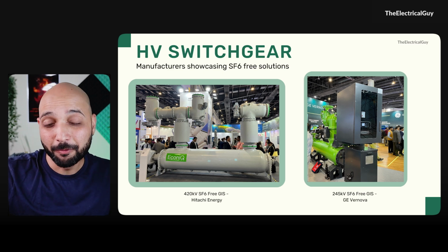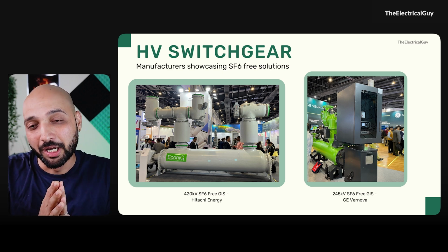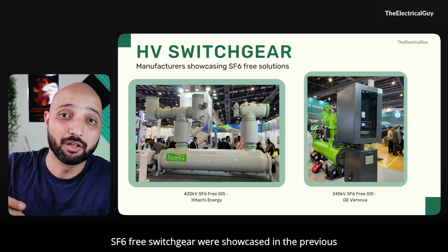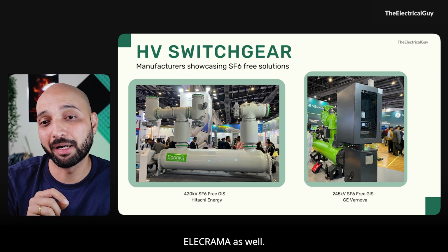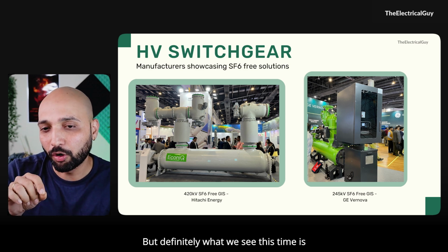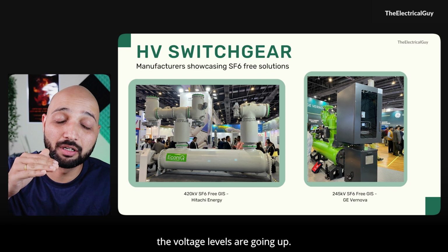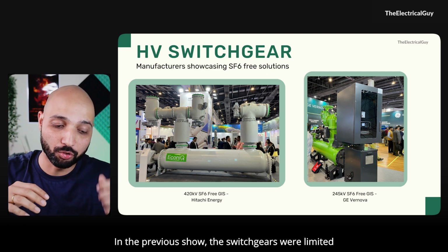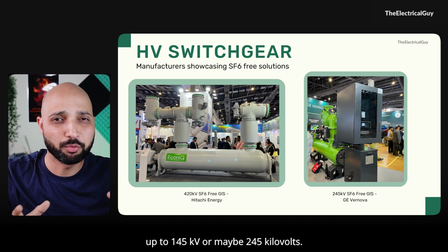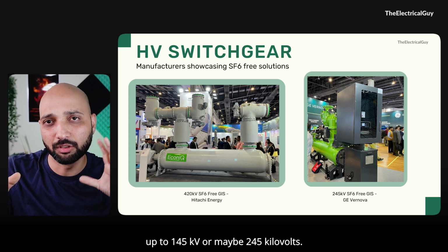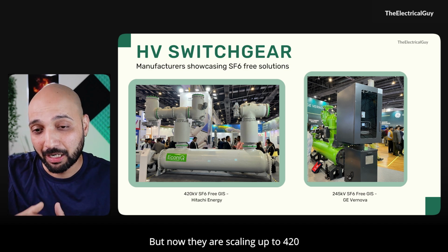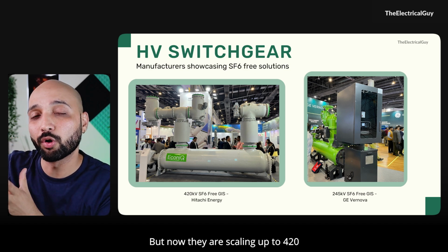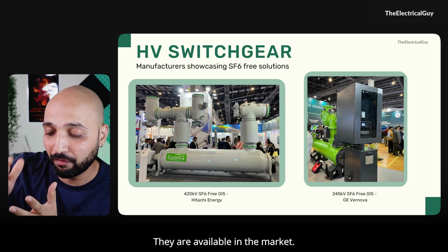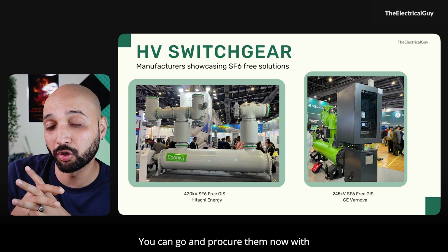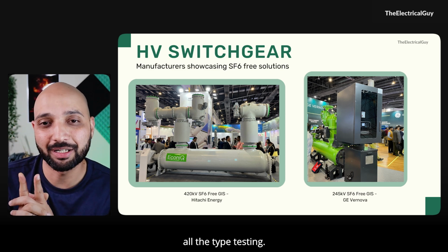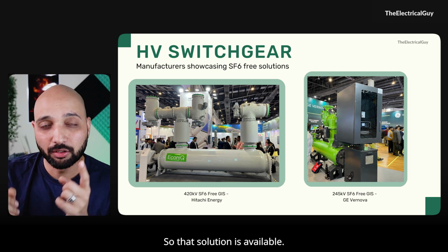Is it new? Well, no. SF6-free switchgear were showcased in the previous Elecrama as well. But what we see this time is the voltage levels going up. In the previous show, the switchgears were limited to 145 kV or maybe 245 kilovolts, but now they're scaling up to 420 kilovolts. They're available in the market, and you can go and procure them now with all the type testing done.